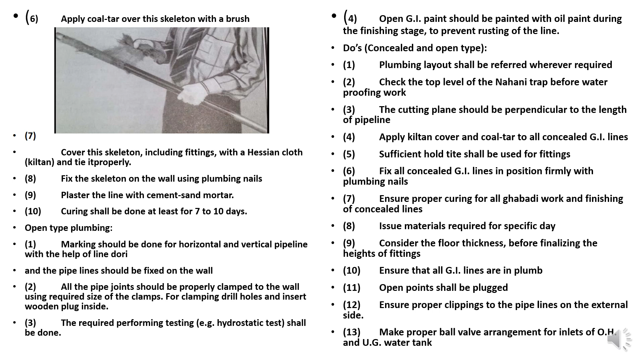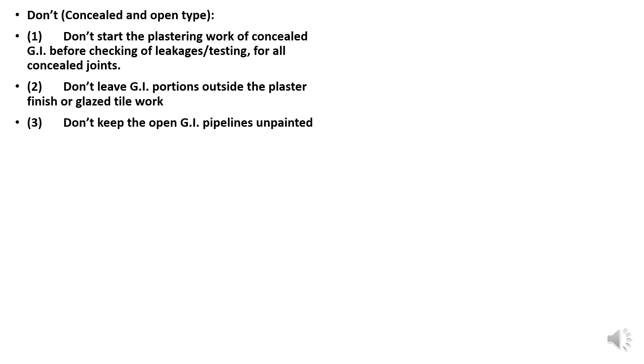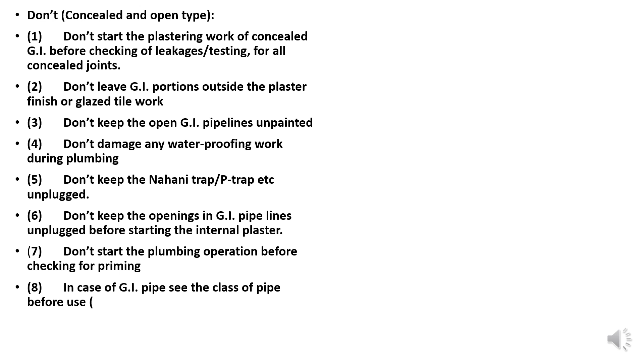Please do not do these things. Don't start the plastering work before checking the concealed piping for leakages. Don't leave GI portion outside the plaster finish. Don't keep the GI pipeline open and unpainted. Don't damage any waterproofing work. Don't keep the nahani trap unplugged. Don't keep openings in GI pipelines unplugged before the starting of the internal plaster. Don't start the plumbing operation before checking for priming. In case of GI pipe, check the class of the pipes, whether it is C, B or A class.